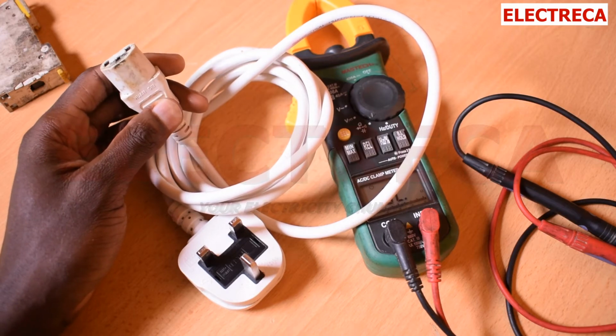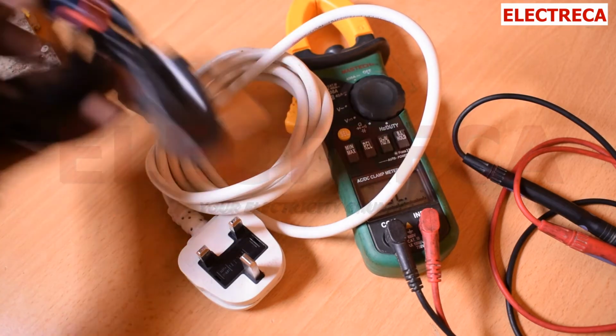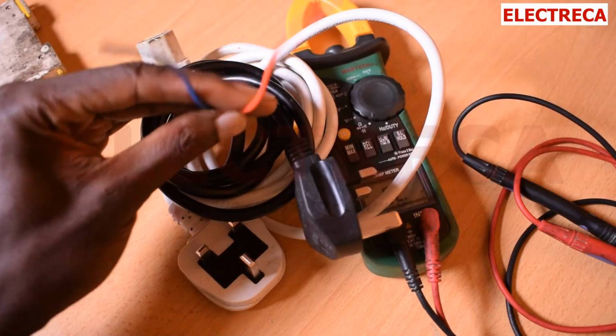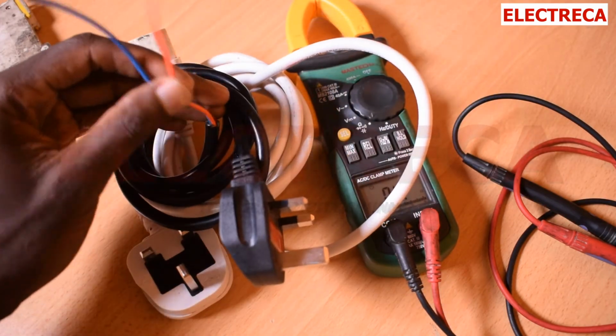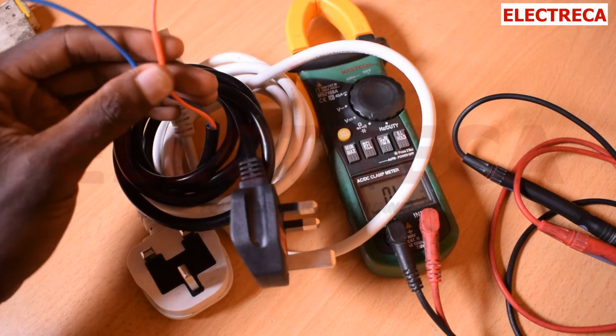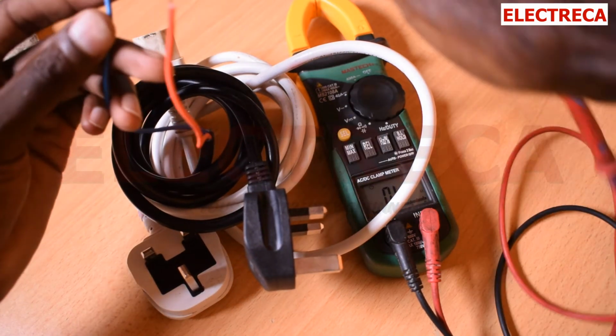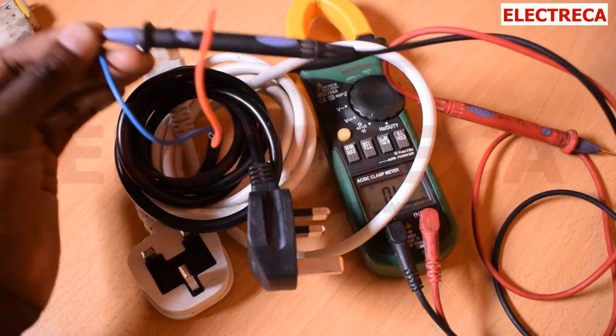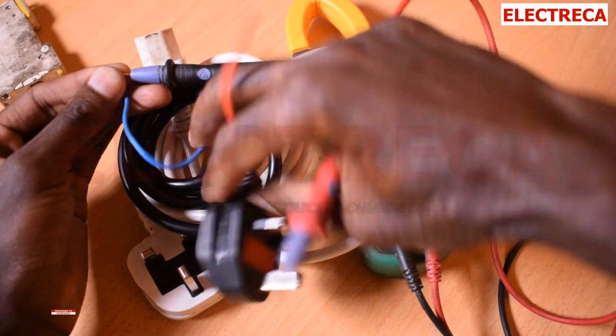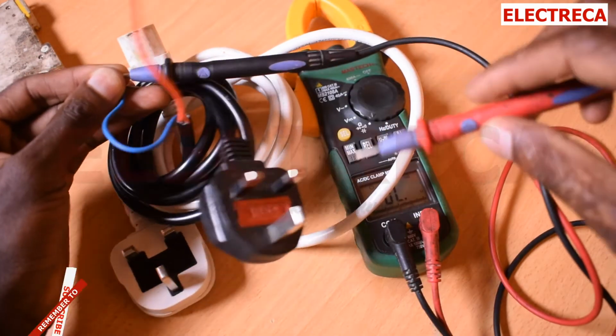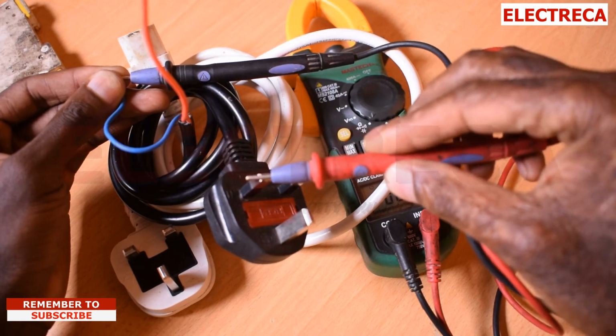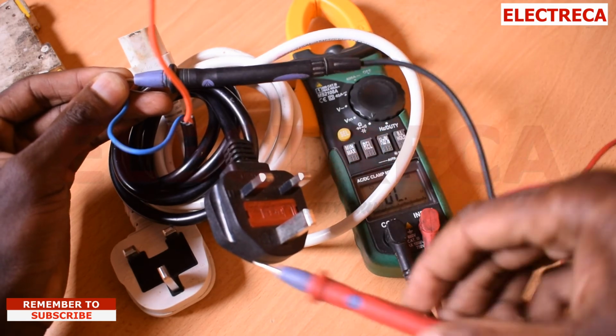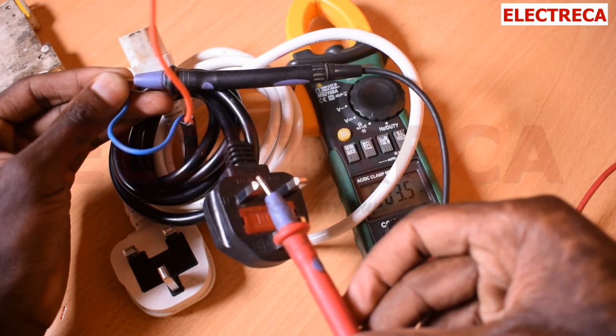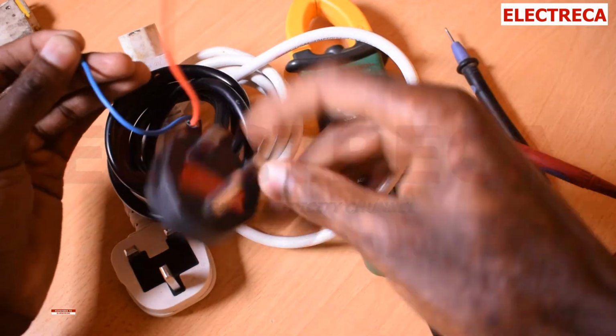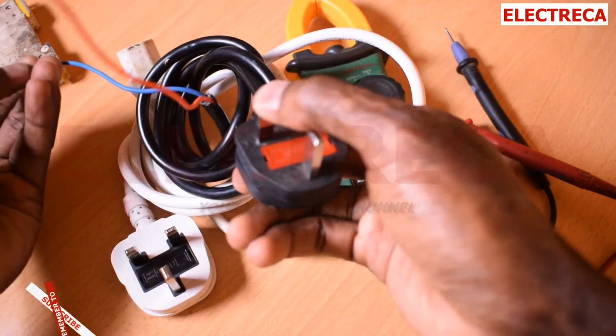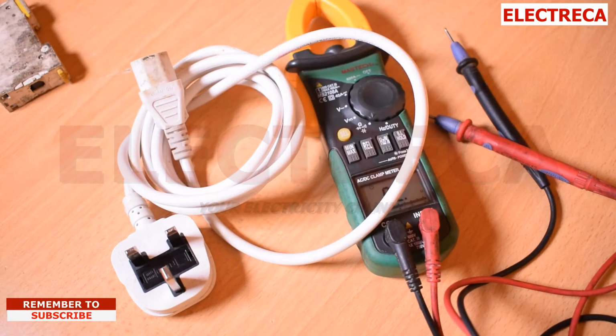Basically, you're going to use the continuity function in your multimeter if you want to identify cables of the same color. Now, assuming these cables were of the same color, and you don't know which one is the live, you'll still use your multimeter, put one lead here, and then move it around the terminals. You move it around the terminals. Now you're able to tell that this terminal here is for this wire.